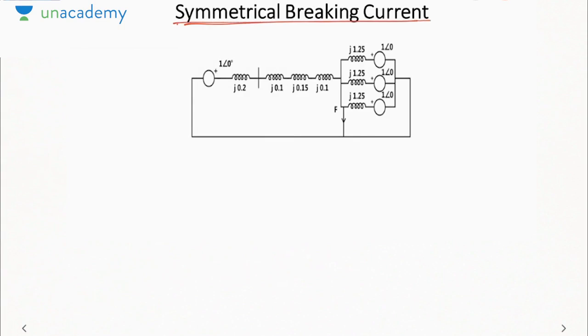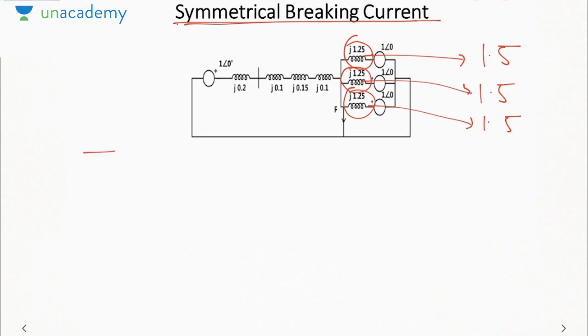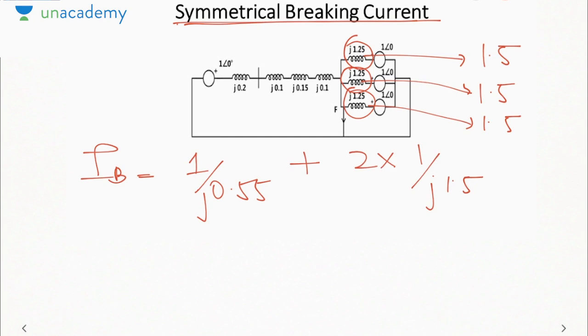And the last rating that we need to calculate is the symmetrical breaking current. But the first rule that I told you about the symmetrical breaking current is that instead of Xd double dash, we have to use Xd dash. Now, here we have used j1.25, so first we will have to replace each with 1.5, because as we calculated, Xd dash is 1.5. Now, the current going into the breaker was the generator current plus the current of the two motors. Okay, because one motor current goes directly into the fault before passing the breaker. So it will be 2 into 1 by j1.5. So how much will this come out to be? Minus j3.1515 pu. Okay, this will be the breaker B current.